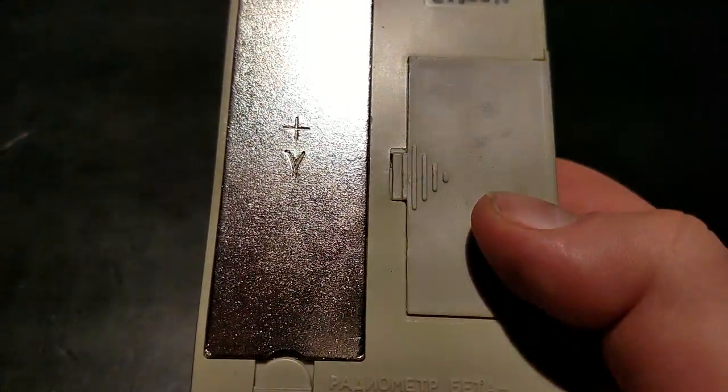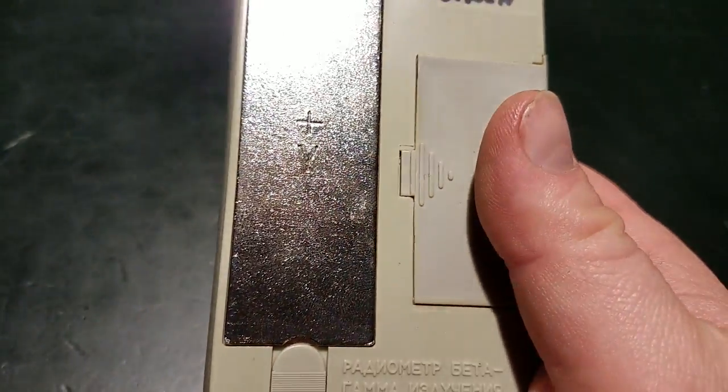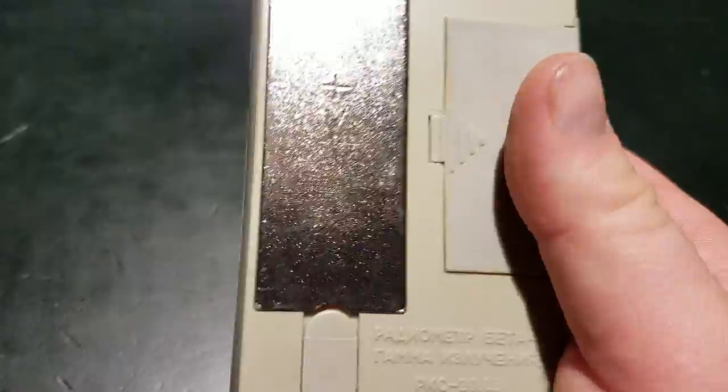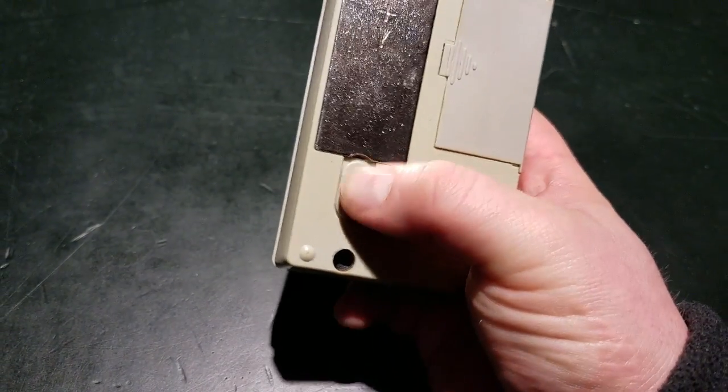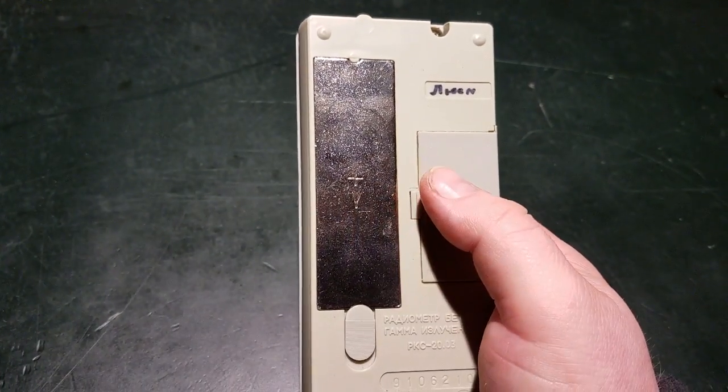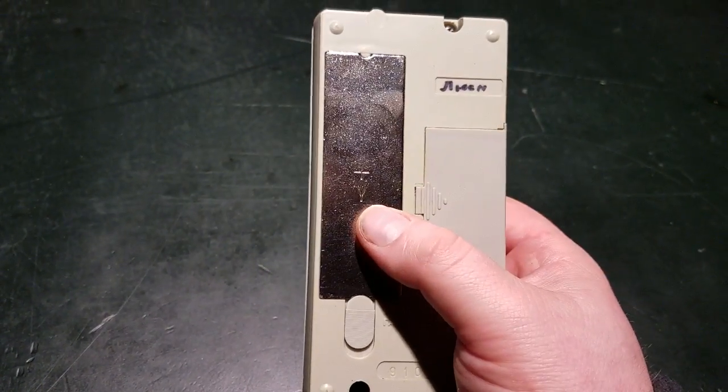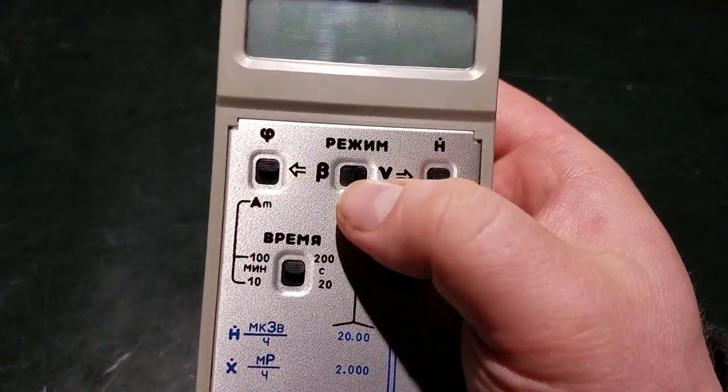With the shield in place, you can see it's got the gamma symbol and a plus showing you where the center of the tubes are. It's got this little thumb switch here which you can use to pull the shield out and put it back in.